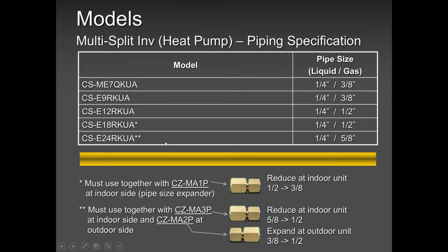For the 24, it's a different story altogether. The 24,000 indoor head uses 5/8 and quarter. So what you're going to do from the outer unit, the suction line, you will run 1/2 inch all the way to the indoor unit. You will upsize it to 5/8 with one adapter and downsize it to 3/8 at the condenser. And the 1/4 inch remains the same 1/4 inch.